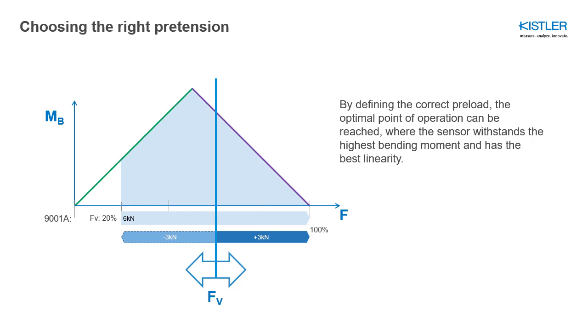But in case you want to have a symmetrical point of operation where you are able to measure not only positive but also negative forces of the same value, you have to choose a preload of 50%. Then you can measure 3 kilonewton positive and 3 kilonewton negative. But keep in mind, as you can see here, when you go to the limit of 100%, then almost no bending moment is allowed anymore. So be careful there. Of course, as we said, one of the biggest advantage of a piezoelectric sensor is the overload capability. There is still some moment that is applicable in order not to destroy the sensor, but still this is a dangerous area to go to when you would like to reach 100% of the sensor.